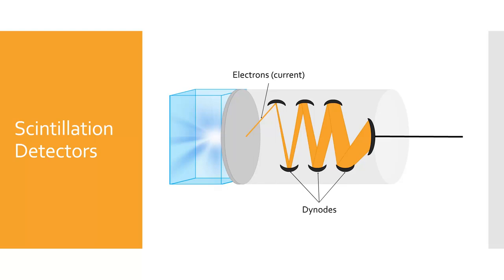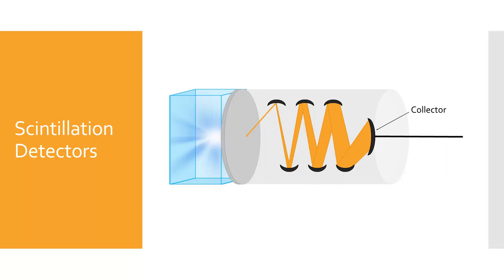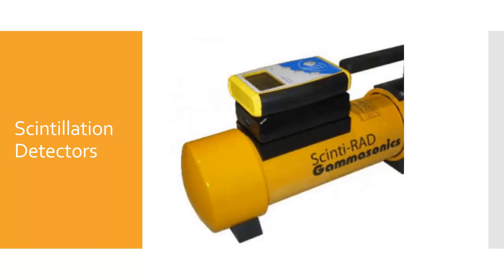The electrical current is amplified by the dynodes of the photomultiplier. Each time a dynode is struck by an electron, several more electrons are produced, resulting in a greater current. This amplified current is directed at the collecting electrode, also called a collector. Scintillation detectors are sensitive to X-rays and gamma radiation, more so than a Geiger counter. This technology is used to create CT and nuclear medicine images, but for our purposes we are more concerned with its use in portable radiation survey instruments. A scintillation detector can register a single photon interaction, which is why it is so sensitive.